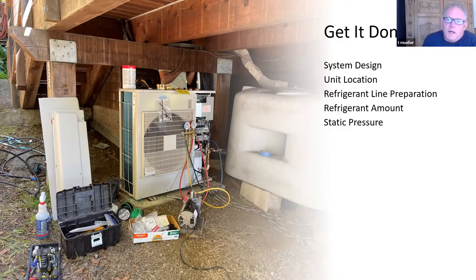The refrigerant amount is another one that's often over the head of the installer, but it has to do with the length of the refrigerant line and the devices attached to it. It's arrived at by checking something called saturated temperature on the system—a relatively complicated concept, but it's important that it's done right, or you'll end up with a system that's not operating at the proper pressures because there's too much or too little refrigerant.